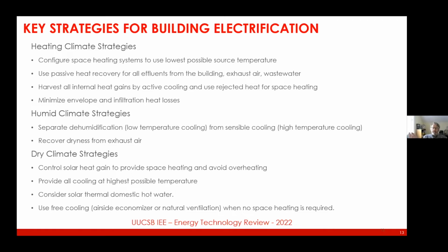And so, for example, if we're making 42 degree water for the dehumidification, we will wind up with a chiller with an efficiency of between 0.55 and 0.6 kW per ton. Whereas if we're making 55 degree water to do the sensible cooling, we're looking at a chiller that's going to be operating at 0.40, 0.41 kW per ton.